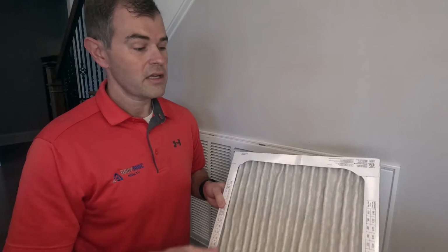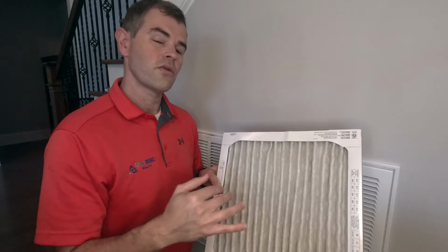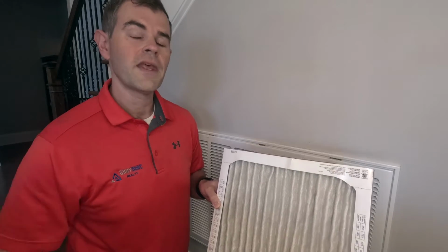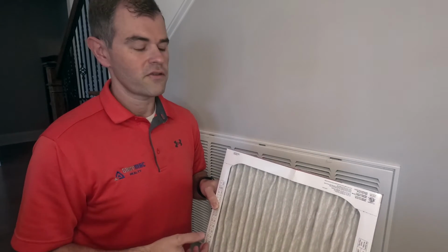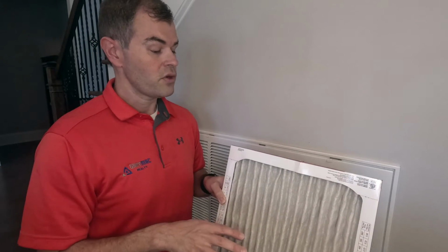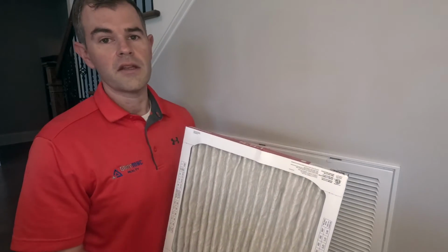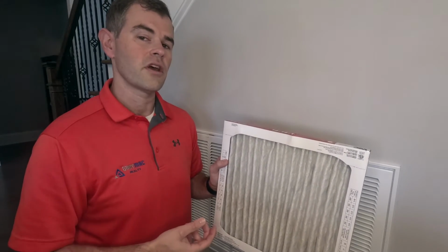So keep in mind with these filters, they are pleated, they have a larger surface area, which helps increase the flow rate without putting a lot of pressure drop on your system. Keep in mind the higher efficiency filter that you go with, the more pressure drop it's probably going to have on your system, which increases the energy required to run your system, and also can increase some wear and tear on your system too. But if you go with a filter that is pleated like this, it helps reduce that pressure drop, and then also really get some air moving through there, and does a really good job filtering.